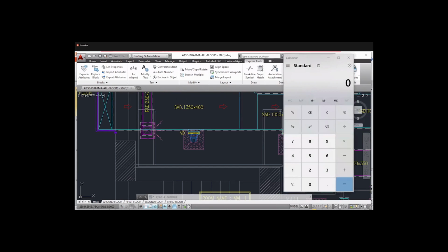No? So 54 inch. So 54 inch into how much? 1 inch is equal to 25.4, so we will take a round of 25. So 1350. So it's matching. No? Our size is correct as per the standard duct velocity and the head loss.